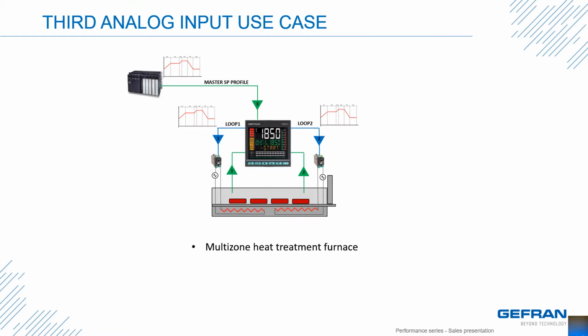What about the third analog input? Expanding on the two PID loop application, maybe we have an analog input from a source like a PLC, or maybe another Performance series controller. The master could be generating a ramp soak profile, but have slave units tracking the master's commands. Maybe we have one master and dozens of slaves tracking the master either exactly or with an offset.